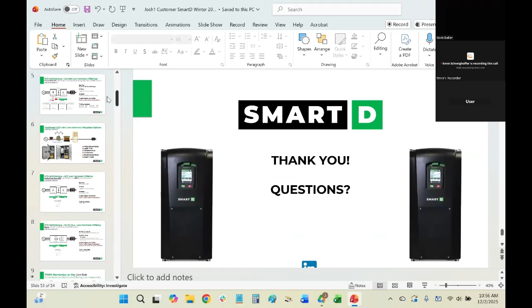I recently did a quote for a customer that had 11 drives in an MCC. Each drive had to have a load reactor, and then they had one huge Mirus filter as a harmonic passive filter on the front end. It's for a lab, and we instead gave them the option to go with the SmartD. They were able to reduce that MCC by 12 feet, and that drastically reduced the MCC price. So now we're just waiting to hear back on how that bid comes along.